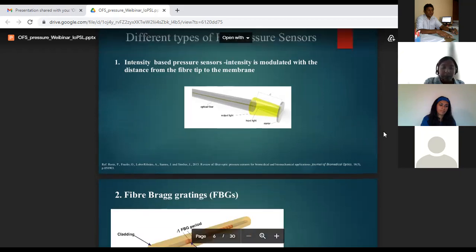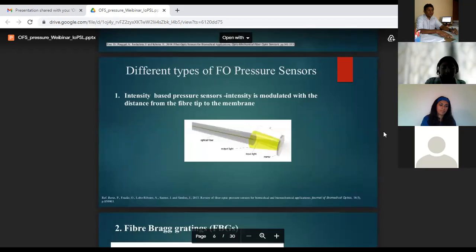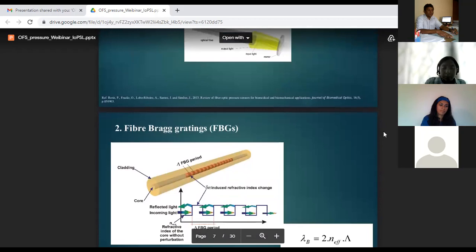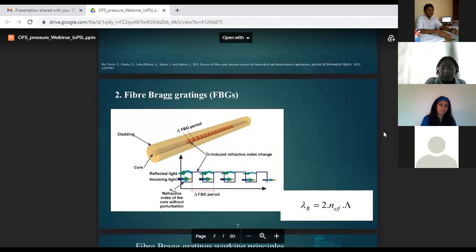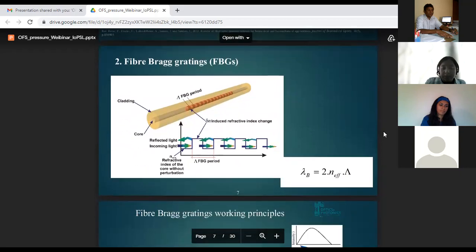And as the diaphragm plane moves further away from this, less light is collected back, and intensity decreases slowly back to zero. So by properly designing the sensor for a selected pressure range, providing that only the monotone region of the light intensity curve is used, a unique pressure could be derived from a light intensity once the sensor has been calibrated properly.